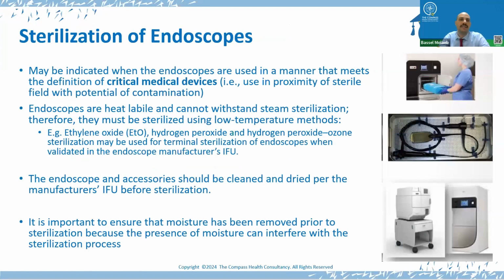So at some instances, sterilization of endoscopes may be indicated, and this happens when the endoscopes are used in a manner that meets the definition of critical medical devices, like getting into a sterile field with potential contamination. At that instant, the endoscopes should be considered for sterilization. Keep in mind that the endoscopes are heat sensitive and cannot withstand steam sterilization.